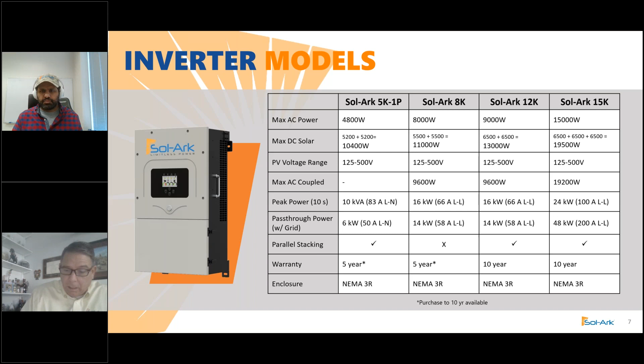We did one that was like a super mansion, I guess, I don't know what they call it, that had two 600 amp panels. As Puya mentioned, you can stack these 15Ks, up to 12 of them, and at 12 you've got 2,400 amps of pass through when you have the grid. And then, as Puya mentioned, 62.5 times 12 is, I don't know, 720, 740-ish, whatever that math turns out to be. But they are very considerable in what they can do for homes on the larger end as well as the smaller end.